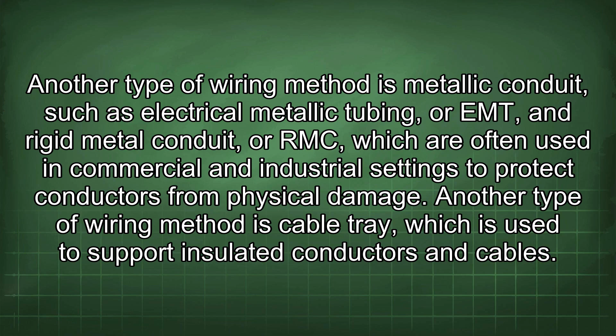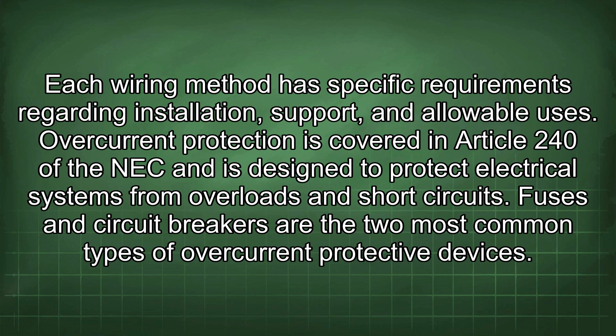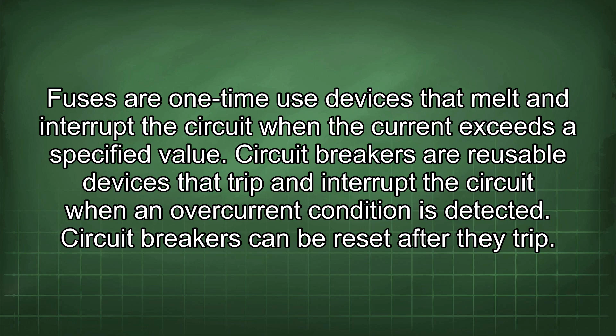Overcurrent protection is covered in Article 240 of the NEC and is designed to protect electrical systems from overloads and short circuits. Fuses and circuit breakers are the two most common types of overcurrent protective devices. Fuses are one-time use devices that melt and interrupt the circuit when the current exceeds a specified value. Circuit breakers are reusable devices that trip and interrupt the circuit when an overcurrent condition is detected. Circuit breakers can be reset after they trip. Properly sizing overcurrent protection is critical to prevent damage to equipment and conductors. The NEC provides tables and guidelines for determining the appropriate size of overcurrent protection based on the ampacity of the conductors being protected.